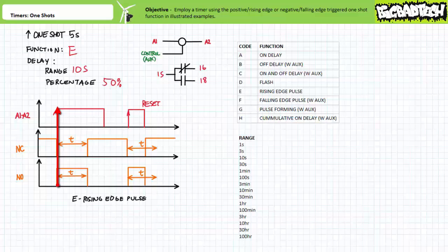Note the one-shot is triggered for a period T on the positive going transition of the coil signal. Note also that this timing diagram illustrates that if the coil was depowered while a one-shot was in process, this particular manufacturer instantly overrides the ongoing one-shot. The coil signal is kind of serving double duty as both the triggering input and the overriding reset signal. Given this behavior, this one-shot is obviously non-retriggerable.